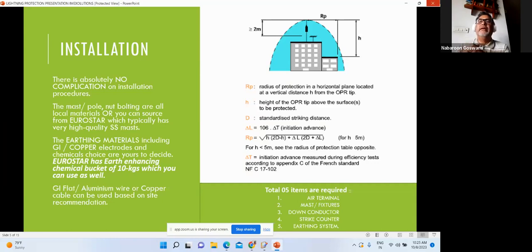There are earth enhancing chemicals available in 10 kg and 20 kg packs that you can use. This is the radius of protection, and there are calculations available as per the site. So there's an air terminal, a mast, a down conductor, a strike counter that we use, and of course the earthing system.